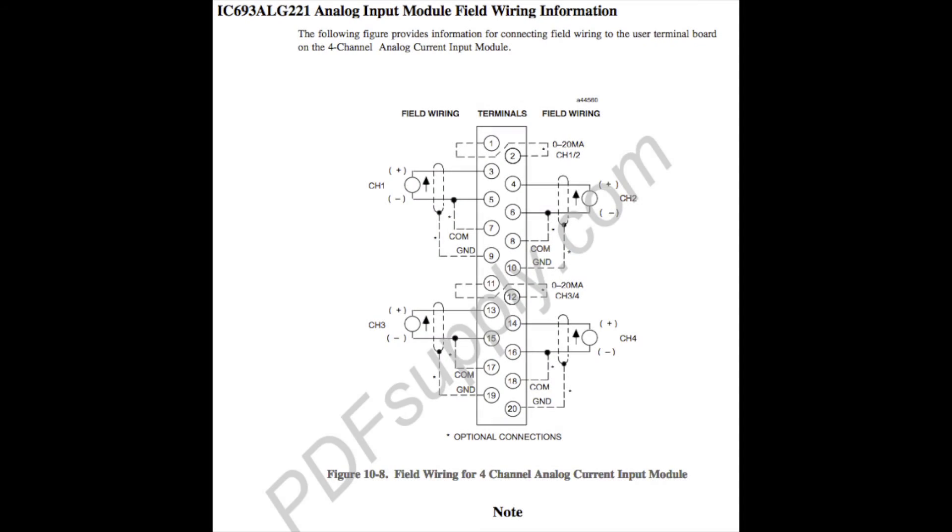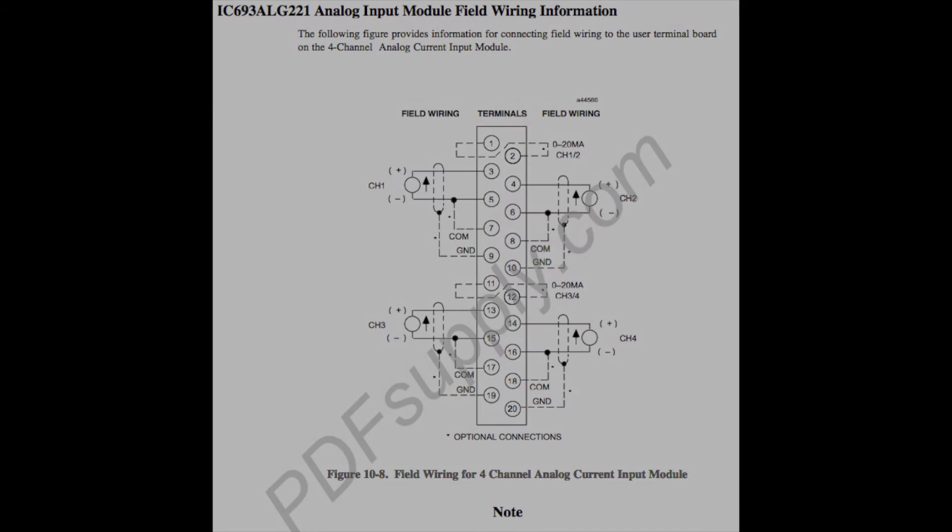Terminal three is positive, five is negative, goes to channel one. Terminal four is positive, terminal six is negative for channel two. Thirteen is positive and fifteen is negative for channel three. And fourteen is positive, sixteen is negative for channel four.